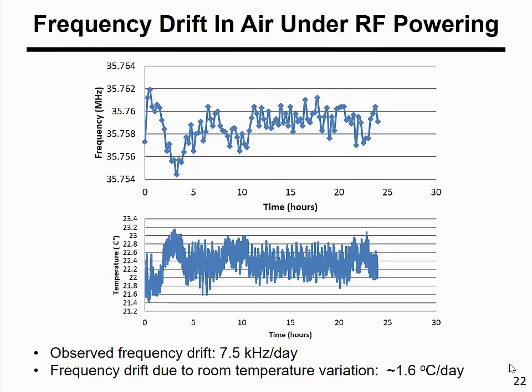So now let's talk about frequency stability. Remember, we had a 5 kilohertz per day frequency drift tested under the DC power condition. Here I recorded the oscillator frequency tested in air and powered by RF powering, without glucose, without hydrogel, without metallic sensing plate, nothing, just the oscillator itself. As you can see, the oscillator frequency drifts around. I recorded the temperature simultaneously, and they carry a similar signature. When there is a temperature increase, the frequency decreases, and when the temperature decreases, the frequency increases. In other words, there is a negative temperature coefficient in the oscillator frequency, even if there is nothing else. Here we observed a frequency drift of 7.5 kilohertz per day under a room temperature variation of about 1.6 degrees Celsius.